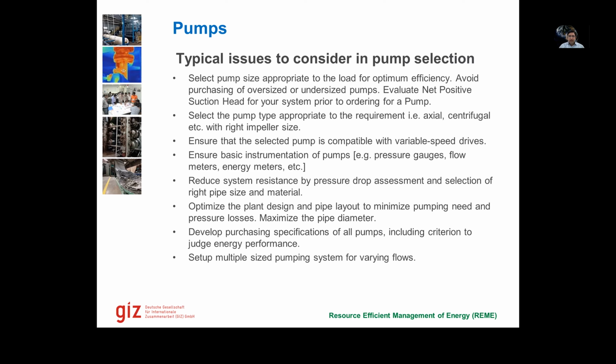And because of that, we once did a calculation of the efficiency, and since the ratings that were provided to us by the factory team were wrong, the efficiency came out to be more than 100%. That already means that the data that was provided was wrong, so we had to skip that data. So it's important that all the motors and pumps have the type plate readings. If they don't have type plate readings, there's no use doing audits of these pumps or motors because we don't have the real data.